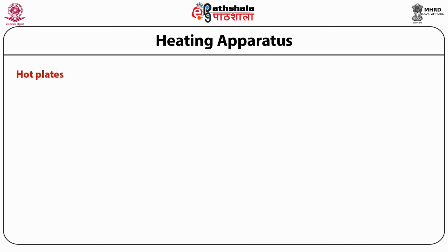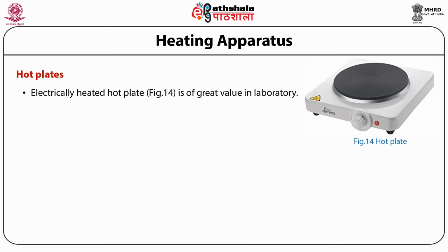Hot plate. The electrically heated hot plate as shown in figure, preferably provided with three controls, low, medium and high, is of great value in the analytical laboratory. The heating elements and the internal wiring should be totally enclosed, which protects them from fumes or spilled liquid.